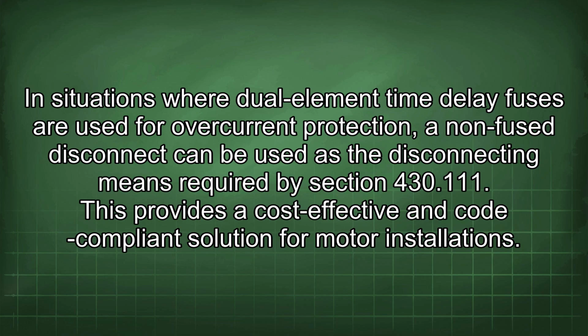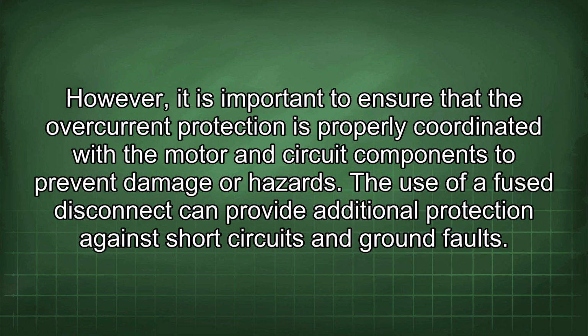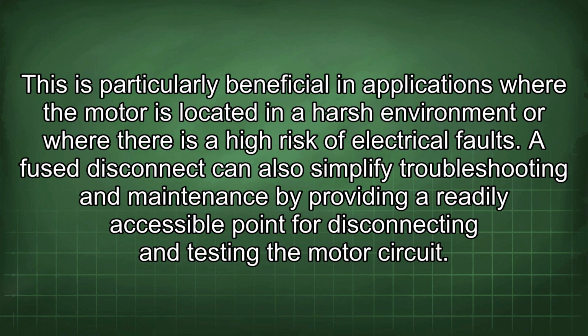In situations where dual-element time delay fuses are used for overcurrent protection, a non-fused disconnect can be used as the disconnecting means required by Section 430.111. This provides a cost-effective and code-compliant solution for motor installations. However, it is important to ensure that the overcurrent protection is properly coordinated with the motor and circuit components to prevent damage or hazards. The use of a fused disconnect can provide additional protection against short circuits and ground faults. This is particularly beneficial in applications where the motor is located in a harsh environment or where there is a high risk of electrical faults. A fused disconnect can also simplify troubleshooting and maintenance by providing a readily accessible point for disconnecting and testing the motor circuit.